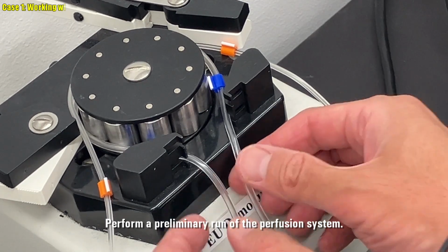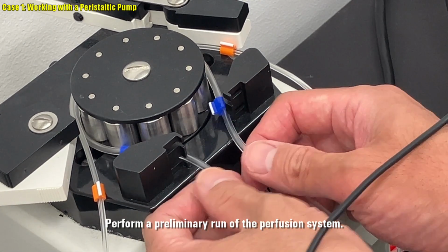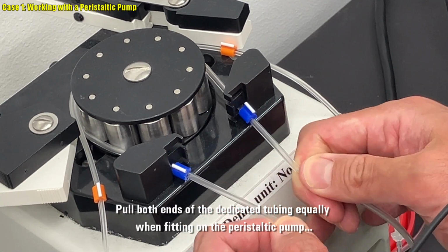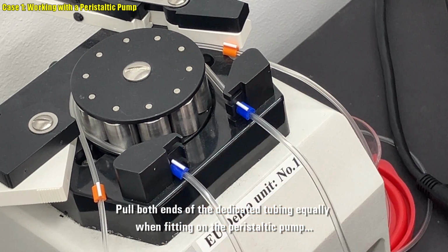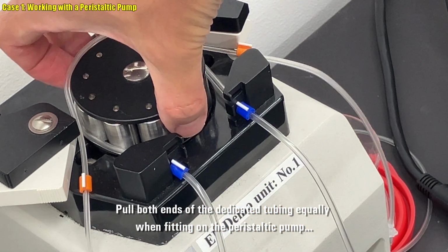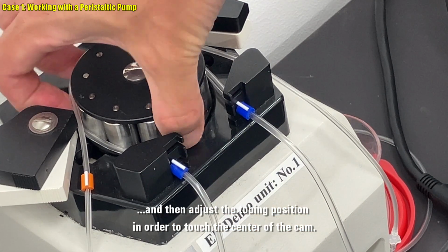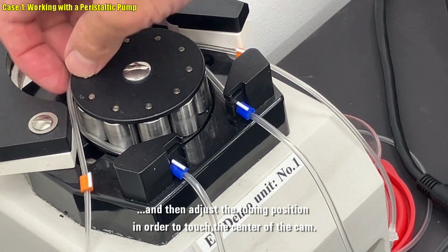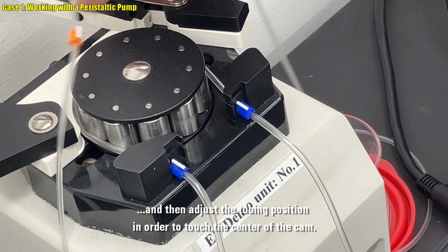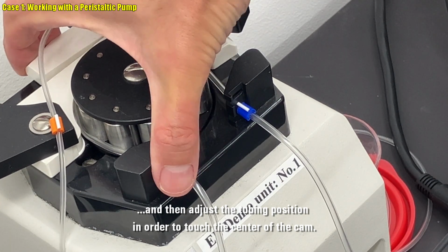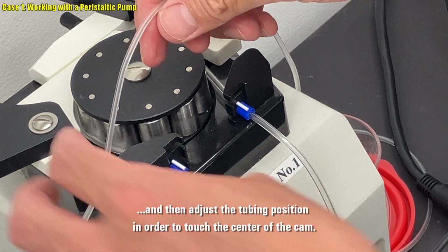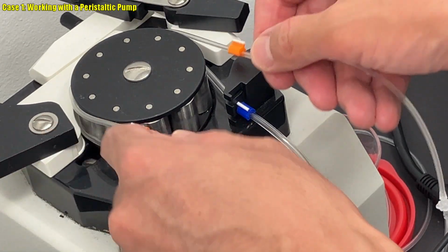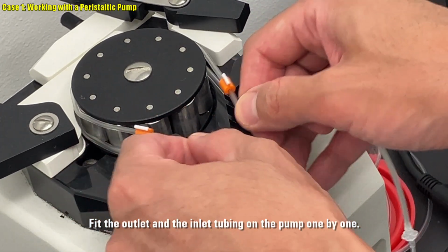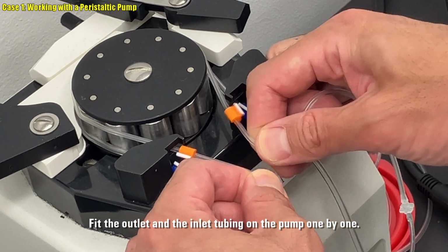Perform a preliminary run of the perfusion system. Pull both ends of the dedicated tubing equally when fitting on the peristaltic pump. And then adjust the tubing position in order to touch the center of the cam. Fit the outlet and the inlet tubing on the pump one by one.